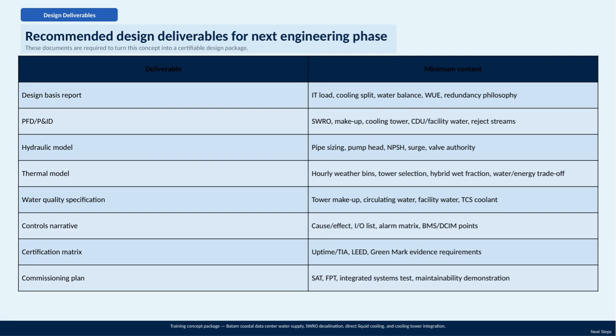For thermal modeling, we'll incorporate hourly weather data, select appropriate cooling towers, define the hybrid wet fraction, and analyze water versus energy trade-offs to optimize performance. Water quality specifications will set the standard for tower makeup water, circulating water, facility water, and the cooling system coolant, ensuring all fluids meet necessary quality levels. The controls narrative will describe cause and effect scenarios, include the input-output list, alarm matrix, and outline building management system, and data center infrastructure management points.